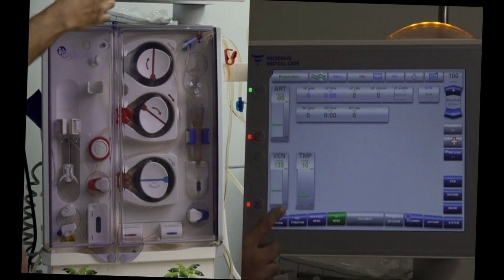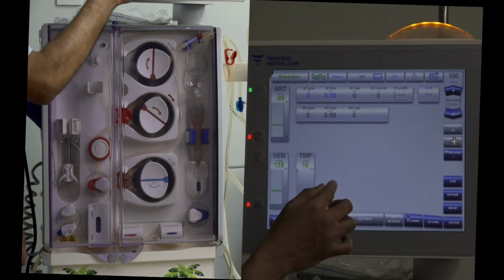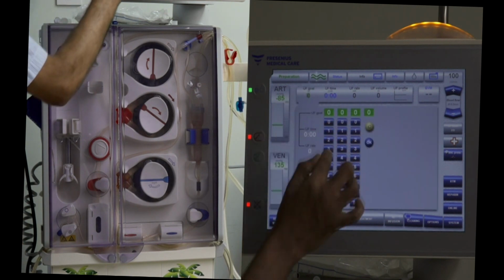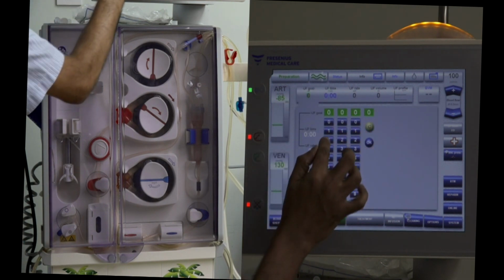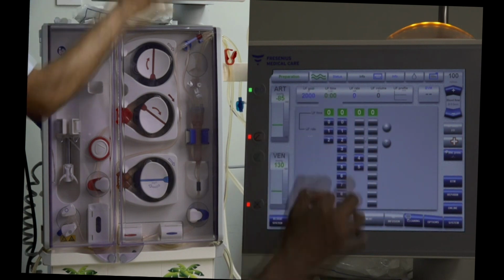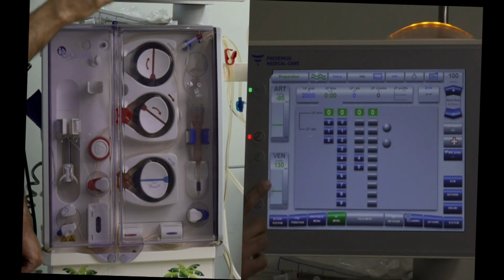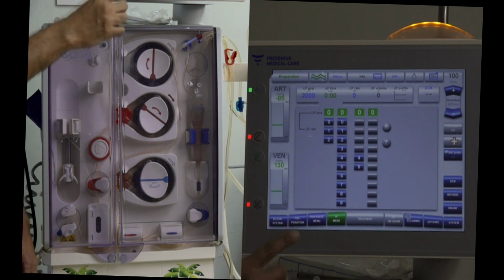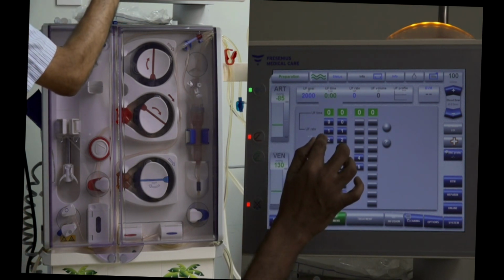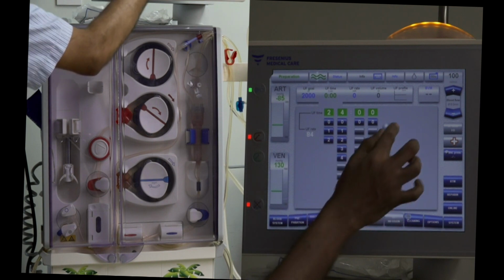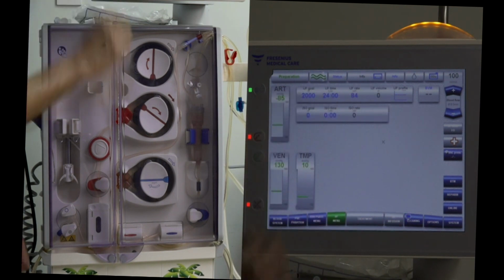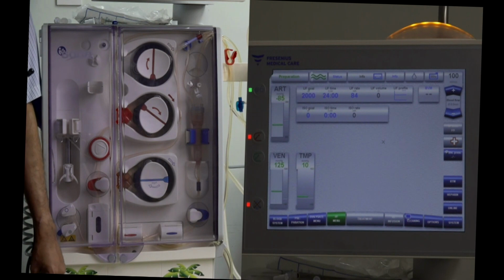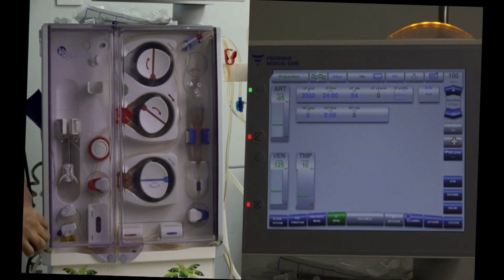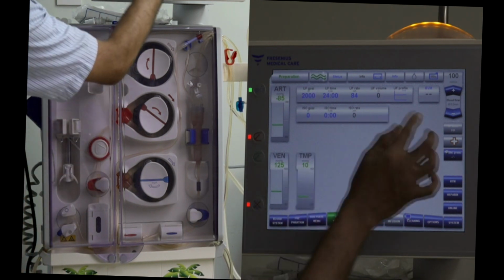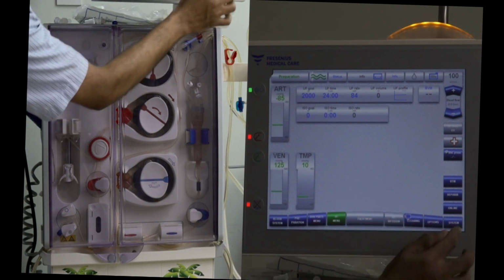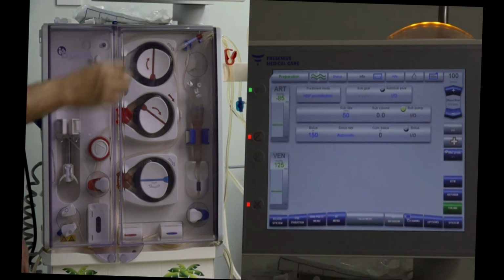Next, we have the ultrafiltration menu, and we need to set our patient's ultrafiltration. So we set an ultrafiltration goal. I'm going to choose 2 liters over here, and unlike in the 4008 series machines where we have a limit of 9 hours 59 minutes, we can do this as in a sled over a period of 24 hours. So we can go down to a very low ultrafiltration rate, which helps to promote hemodynamic stability in our ICU patients. So I'm going to accept that, and now I can choose my online hemodiafiltration.